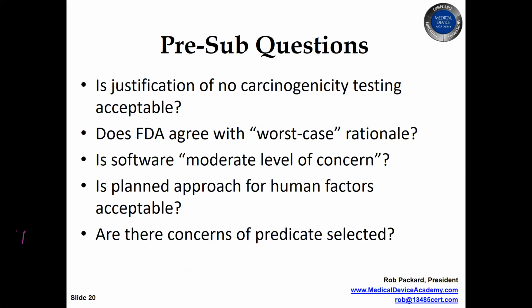Well, if that's your plan, you need to submit a biological evaluation plan, or BEP, as part of your pre-sub. So now, yes, it's not required that you do a pre-sub, but if you want the FDA to agree to your biological or biocompatibility testing plan, that BEP, you probably ought to submit it ahead of time in a pre-sub. And if you want to get out of certain tests, so there are certain tests now that we can do in vitro instead of doing in vivo animal testing. If you want to save some animals, you have to submit that protocol to the FDA in advance as part of the pre-sub. So just on biological testing alone, there's a lot of biocompatibility tests we're getting out of with these pre-sub meetings.